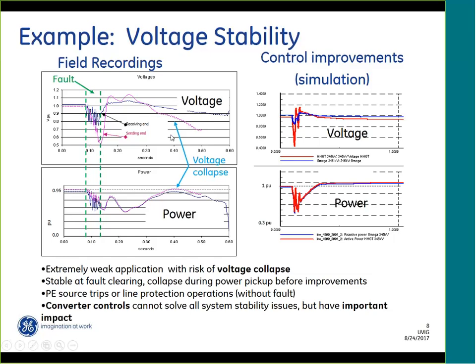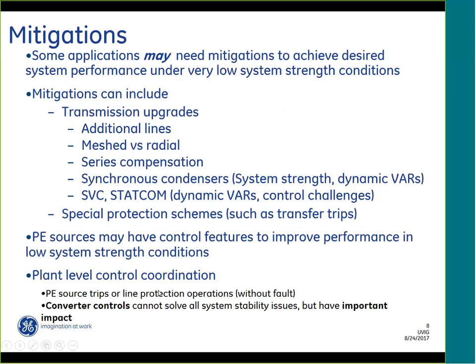In this case, it was possible to modify the wind turbine voltage controls and the plant level controls, basically coordinated plant level controls, to provide more reactive power during the power pickup, and that resolved the problem. This is a simulation showing the improvements, but the system has been operating for many years. Generally speaking, I should say that in both of the examples I provided, it was possible to modify the controls to solve the problems. There is a limit to system stability, and it's not that all the problems can be solved with converter tricks. In this particular case, that was possible.